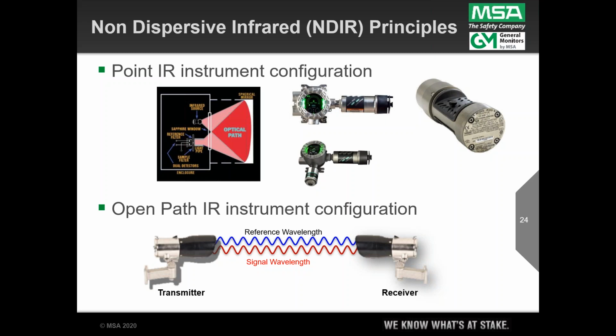It's a much more powerful lamp type. It's a xenon flash lamp rather than an incandescent lamp. But now we've got an instrument that can be used to monitor a perimeter of up to 100 meters plus in total weight and total physical distance, and any hydrocarbon cloud basically migrating into that beam of light will absorb the same frequency just like the point IR detector, and the receiver module will measure that absorption and provide an output that represents the total molecular hydrocarbon content in the beam.